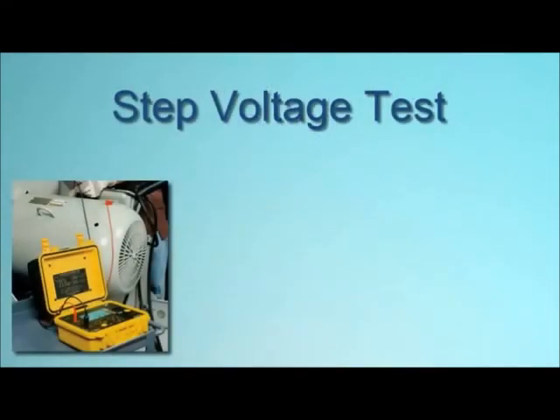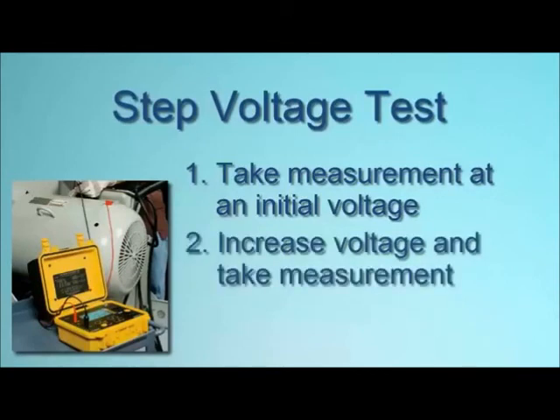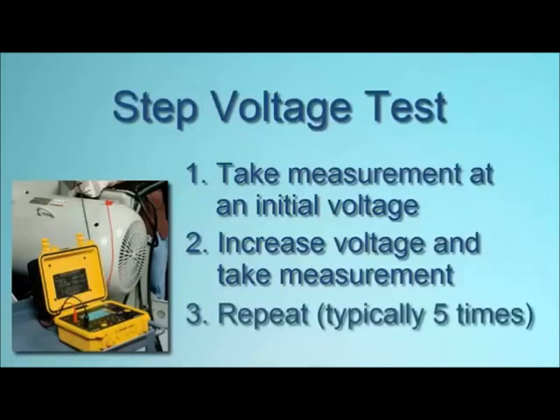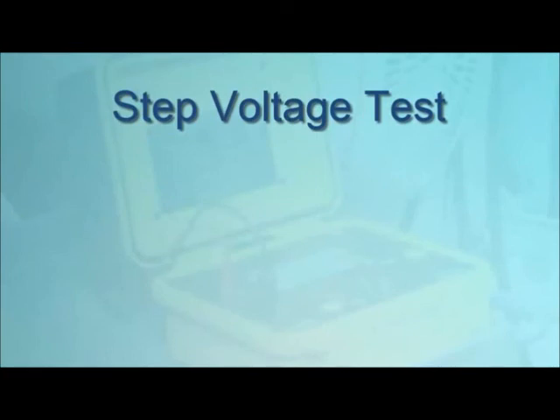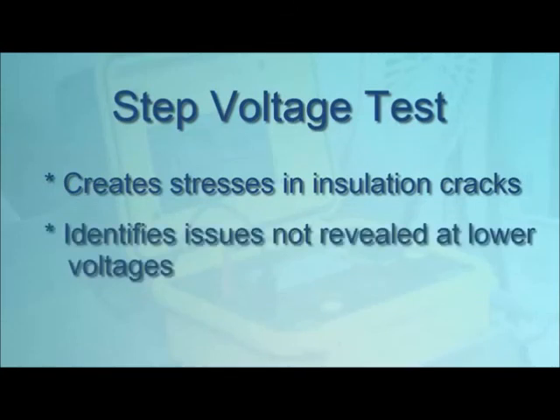A third method is the step voltage test. This involves testing at two or more test voltages and comparing the results. The test begins at an initial test voltage; at a specified interval, typically one minute, a measurement is recorded, after which the test voltage is increased — usually to five times the initial voltage. This process may be repeated through several steps, with measurements taken after one minute and the test voltage increased at a 5-to-1 ratio over the previous voltage. A common practice is to test at five voltage steps. The step voltage test is designed to create electrical stresses on internal insulation cracks, identifying potential problems that may not be revealed by testing at lower voltages.